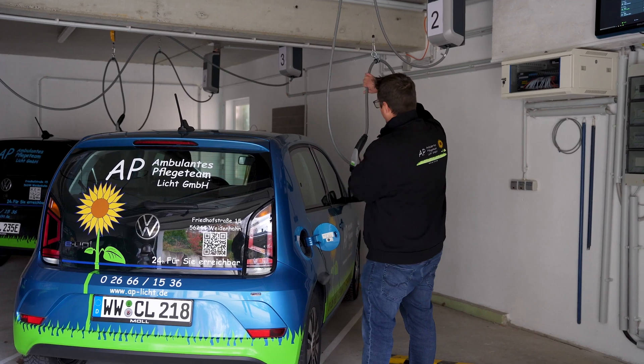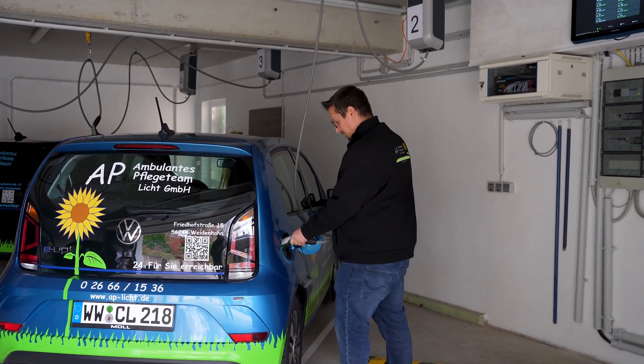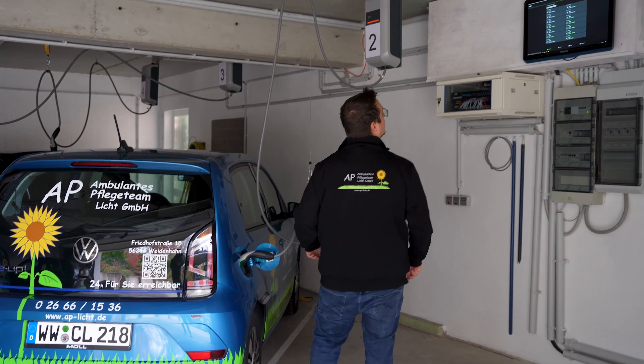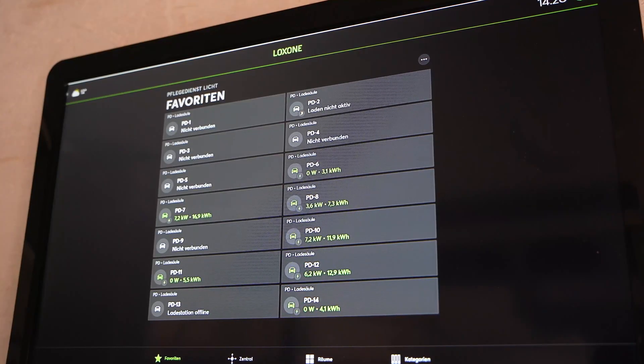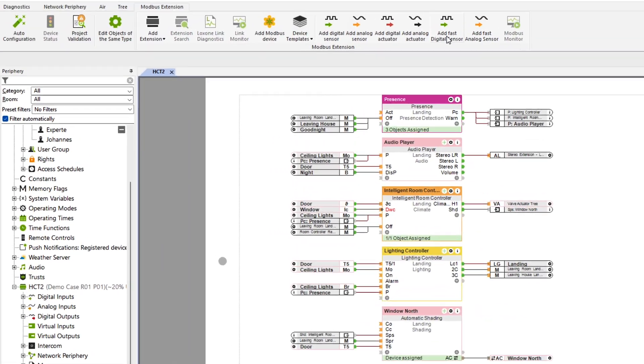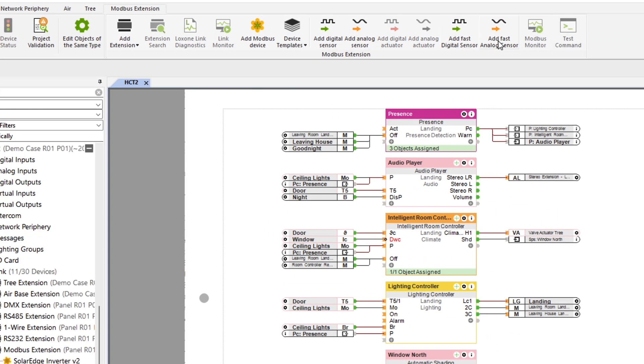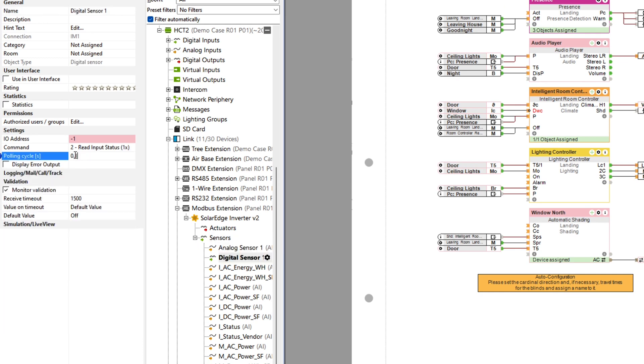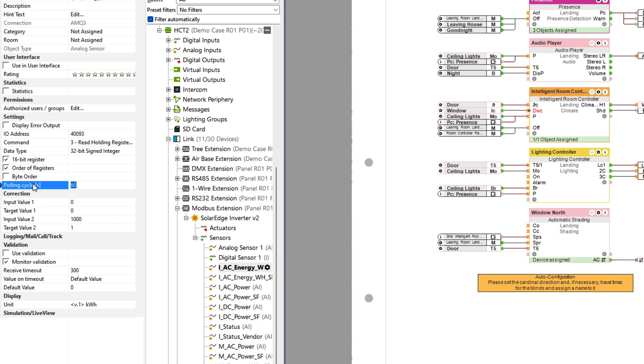Modern energy management involves the requirement to react very quickly to changes in performance in order to avoid load peaks, for example. An example here could be an electric car charging park if several wallboxes are in operation at the same time, and a quick reaction is required in order not to exceed maximum performance. Thanks to the new Modbus high performance inputs, it is now possible to set a minimum query interval of up to 0.1 seconds with 2 Modbus inputs per device. In general, the minimum query interval has been reduced from 5 seconds to 1 second. The air products Modbus Air and the wallbox Air are excluded from this feature.